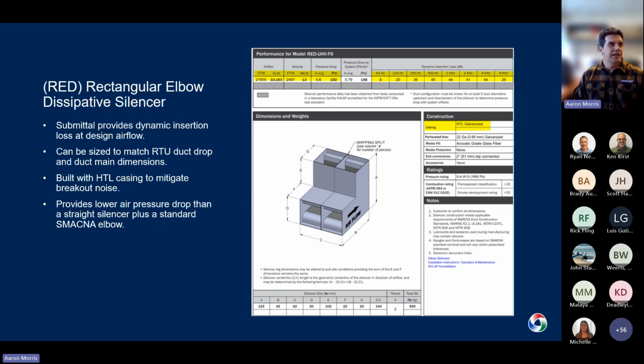Some benefits of using an elbow. One, you can see that we needed a lot of attenuation in this case, so our center line length is 144 inches. If this were a straight attenuator, it would take up 12 feet of space, but by using it as an elbow, we can divide that between the 2 legs of the elbow. And then the air pressure drop of this elbow comes in less than a SMACNA 90-degree elbow plus a 12-foot straight silencer would have. So it's a better option for your air pressure drop.